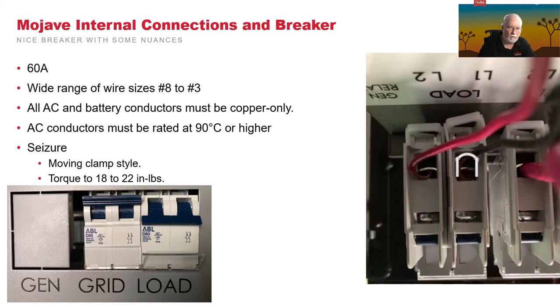They're a little different. But all you have to do is there's a small bracket here on the back. This bracket can be removed. What this bracket does back here is that it allows you to remove the DIN breaker. Now remember, these are dual gangs, so there's two of these little settings here. Pull down on both from the front. You can just reach back there, possibly with an insulated screwdriver. Pop one down, pop the other one down. The breaker will release. Then you can look at it, put the wire in it, and tighten the screw to make sure you clamped it correctly.